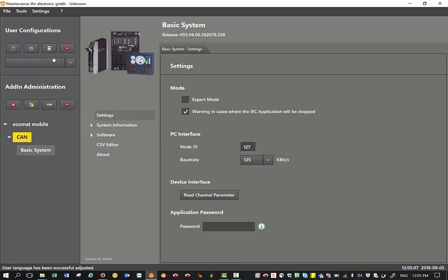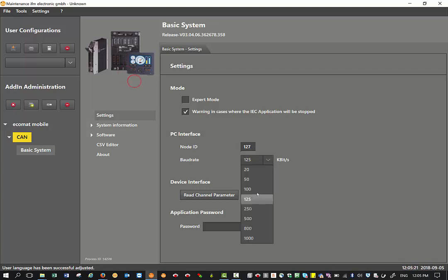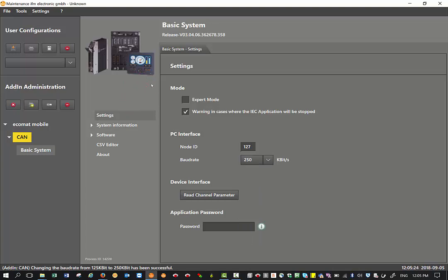Here it's very important to put the default settings from the factory. In our case, the basic controller CAN interface one has a node ID of 127 and a baud rate of 250, so we select 250 here.